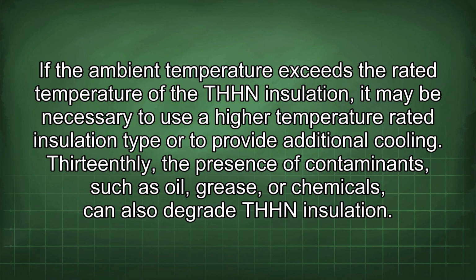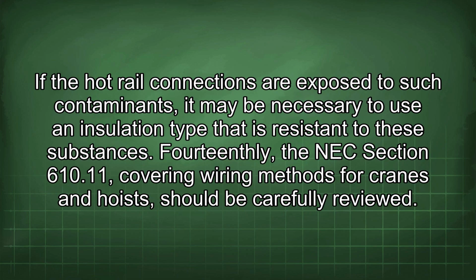If the ambient temperature exceeds the rated temperature of the THHN insulation, it may be necessary to use a higher temperature rated insulation type or to provide additional cooling. 13thly, the presence of contaminants such as oil, grease, or chemicals can also degrade THHN insulation. If the hot rail connections are exposed to such contaminants, it may be necessary to use an insulation type that is resistant to these substances.